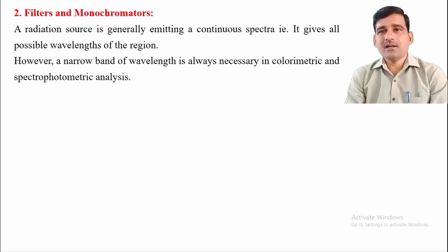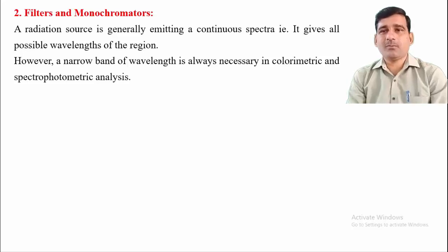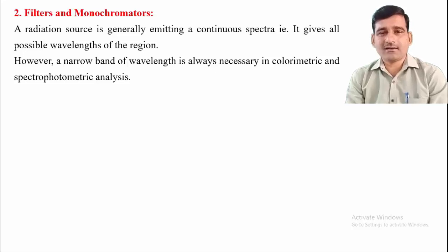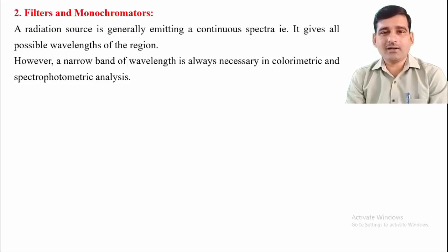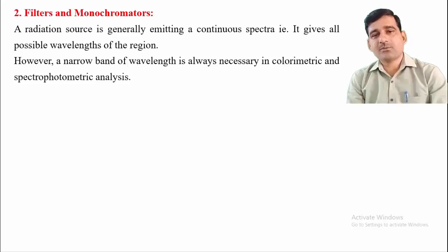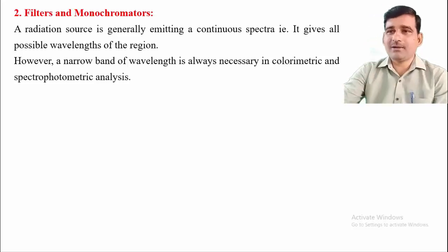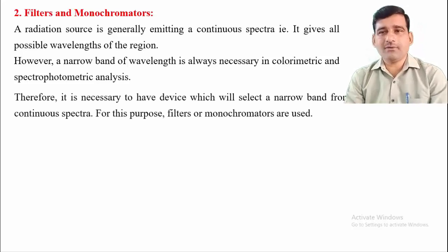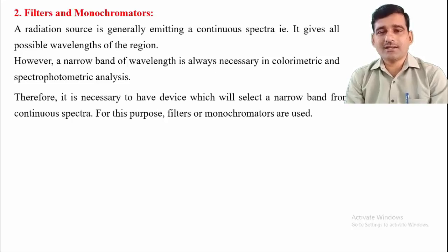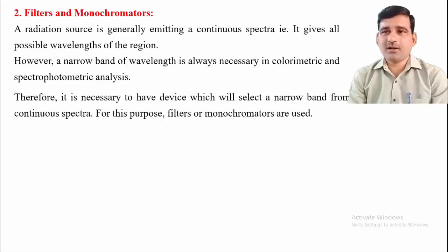A narrow band of wavelength is always necessary in colorimetry as well as spectrophotometric analysis. For example, if we require 580 nanometer wavelength, we use a narrow bandwidth of plus or minus 10 nanometer or sometimes plus or minus 25 nanometer. It is therefore necessary to have a device that selects a narrow band from the continuous spectrum, and for this purpose we require filters and monochromators.